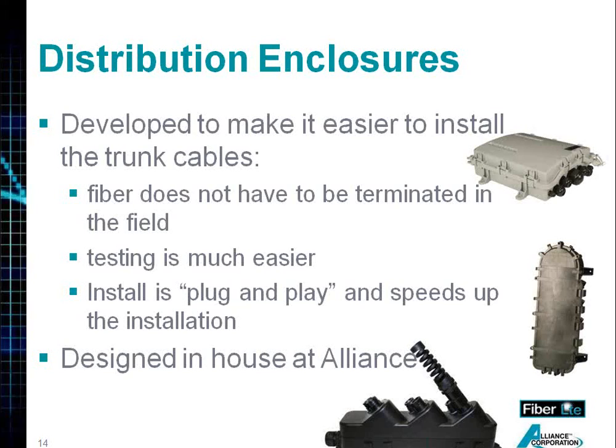The fiber and power cables, when they're manufactured and delivered to site, are typically broken out and terminated at one or both ends and fed into distribution blocks or separate plug-and-play modules. The plug-and-play modules work really well as there's no handling of the individual fibers, and they speed up the installation time.